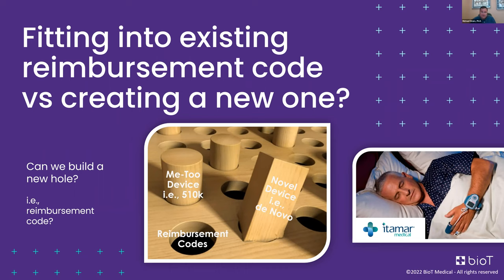The essence of the 510K is basically that we have to show our device is substantially equivalent to another device already on the market, what we call a predicate device. It stands to reason that if there's another device very similar to ours already on the market, there's probably a reimbursement code that device fits into that our device will probably fit into as well.